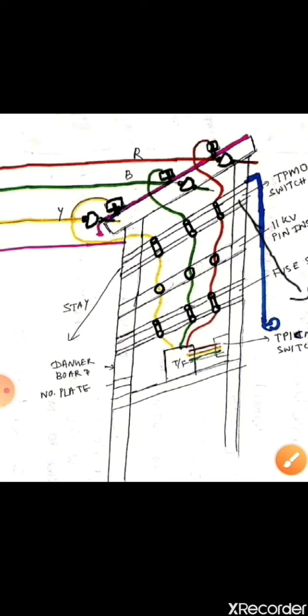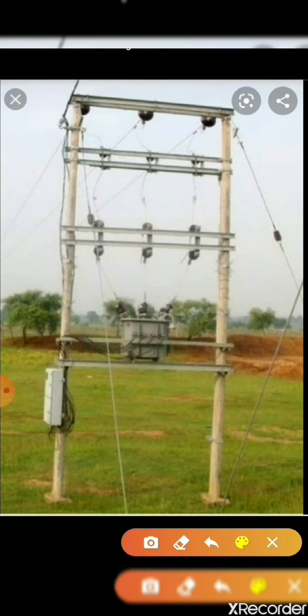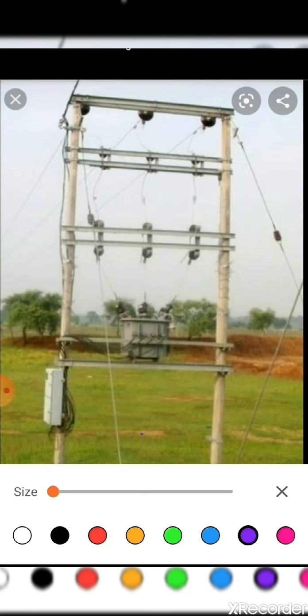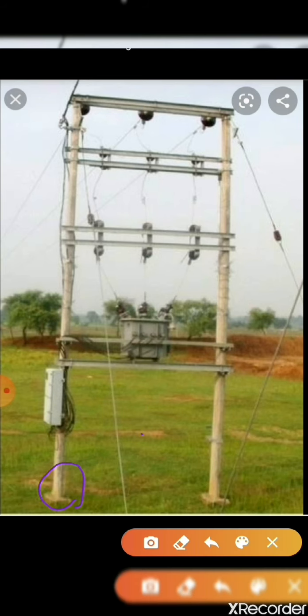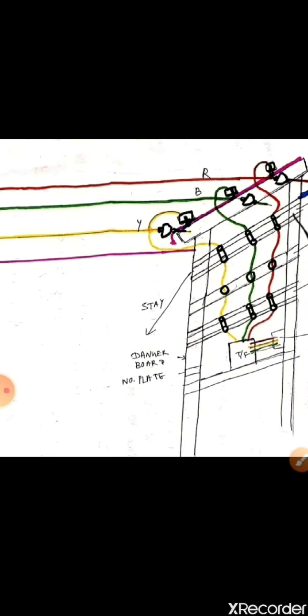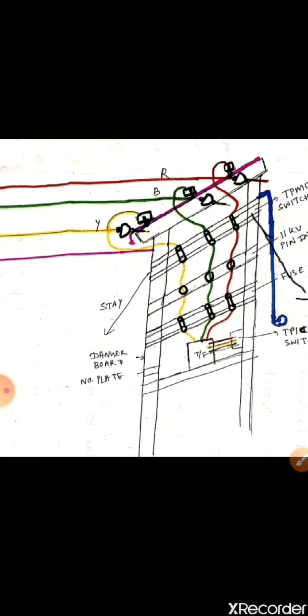Next, the fittings on HT double pole structure for the pole mounted substation. The material required for the pole mounted substation, first one is stone pad. Here in this diagram you can see the stone pads. Here the stone pads are there to give the mechanical strength to the poles. So the requirement of stone pad is 2 numbers.